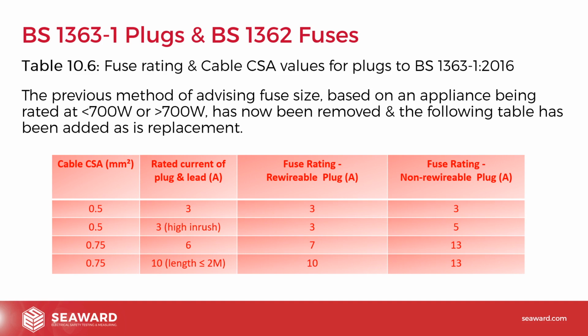So this is the information that the manufacturer would be using when they actually manufactured, or when they chose their fuse for the particular equipment. So from that side of things, using the table actually means that we're using more of what the manufacturer would have used in the first place. Obviously, the aim, as we said on the previous slide, is to use the manufacturer's preferred fuse rating. So if the manufacturer has specified a 5 amp fuse, then we'd want to use a 5 amp fuse. If they specified a 3, we'd use a 3, and so on. But by using the table now that's been included in the new code of practice, it should give you a better idea of why the manufacturers have chosen what they've chosen.